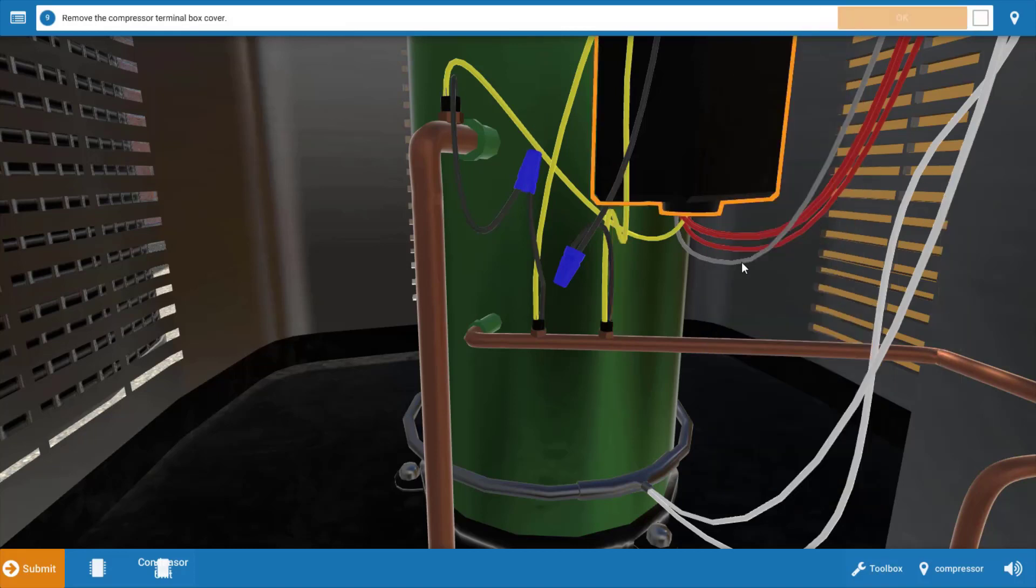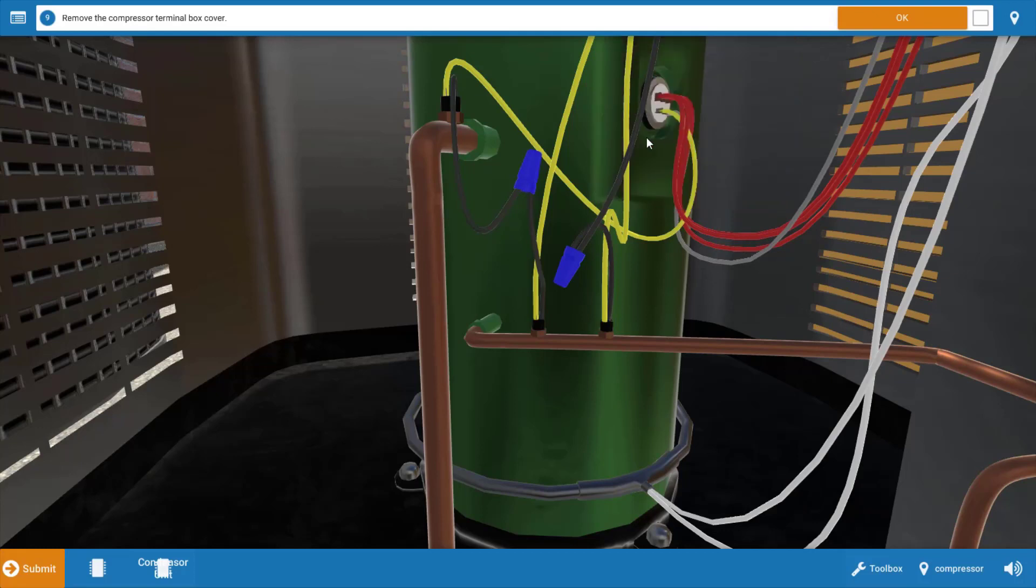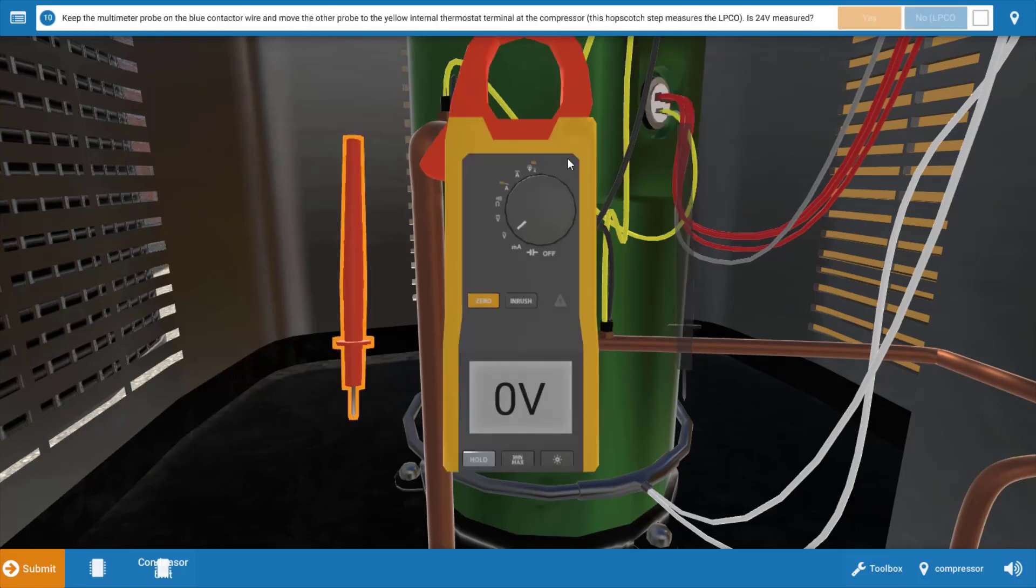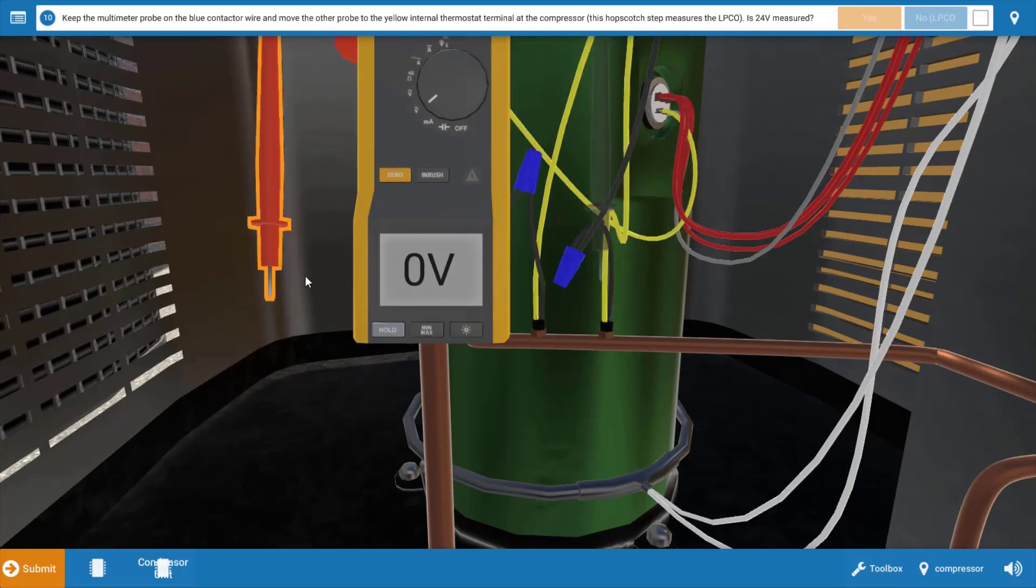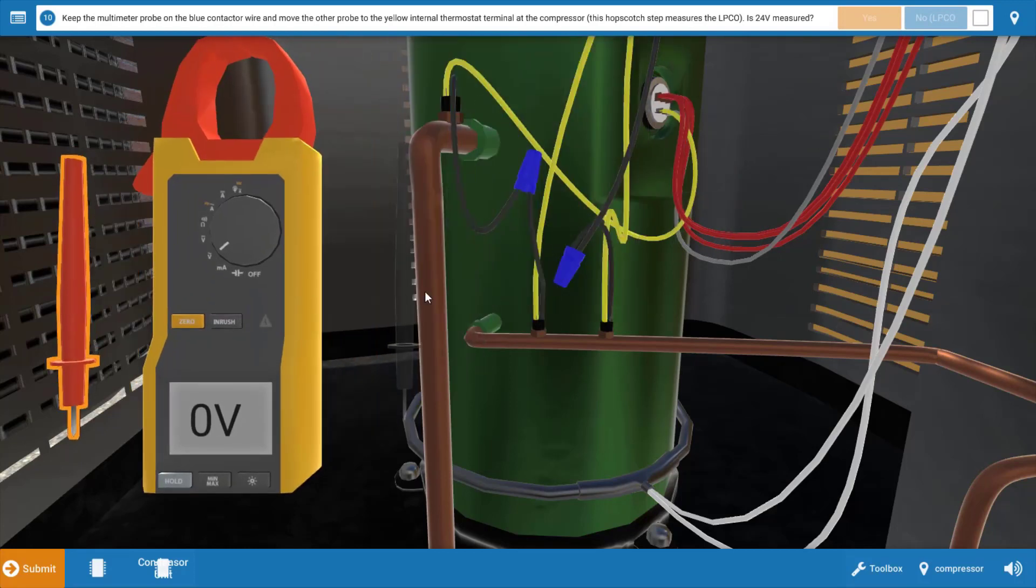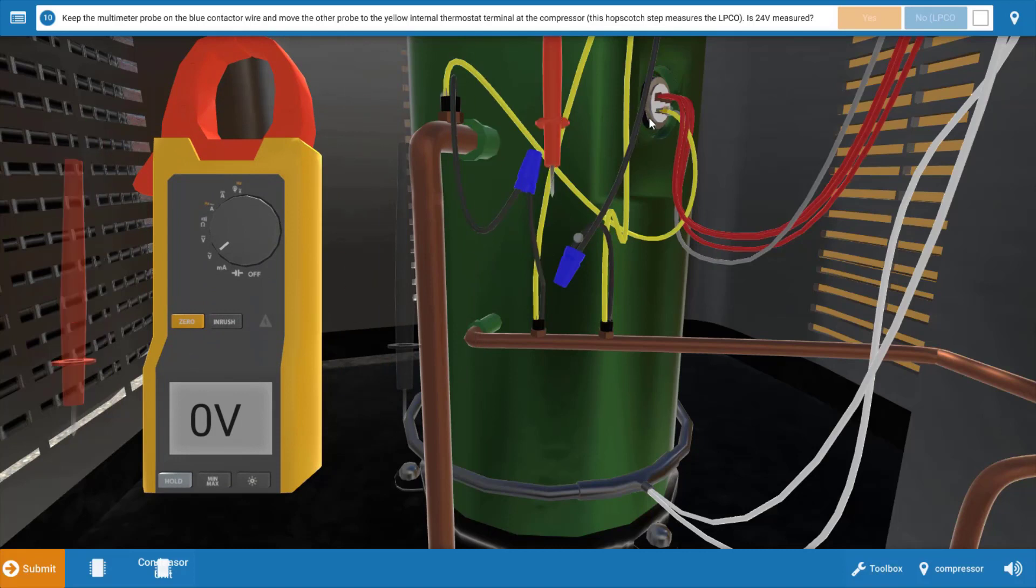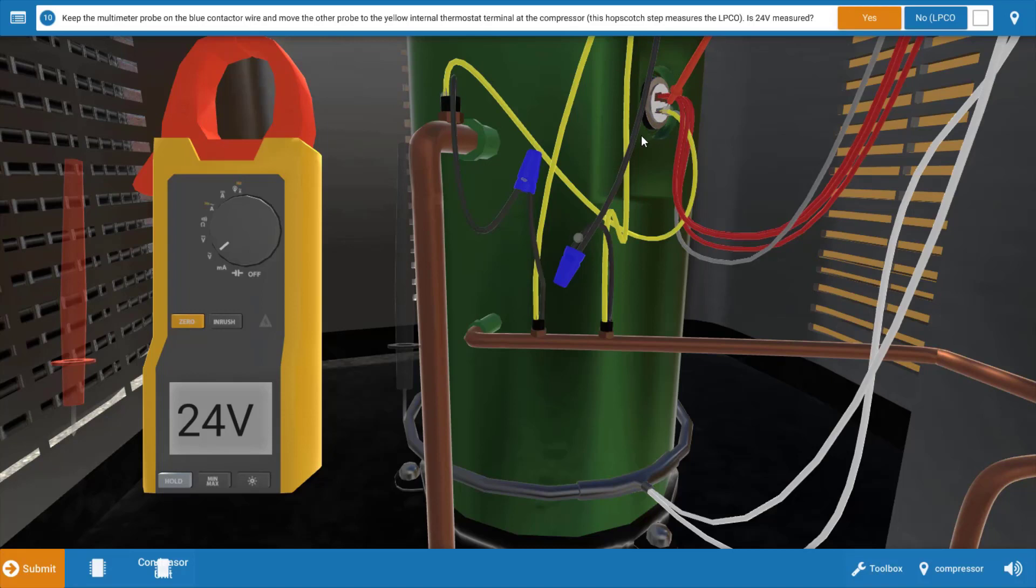Now to check the low pressure cutout, we're going to need to remove the terminal box cover and check it at the line input to the internal thermostat. I'm going to slide my meter lead out of the way and place my red lead over here on the line connection of the internal thermostat, and we have 24 volts. Again, this verifies that our low pressure cutout is closed.